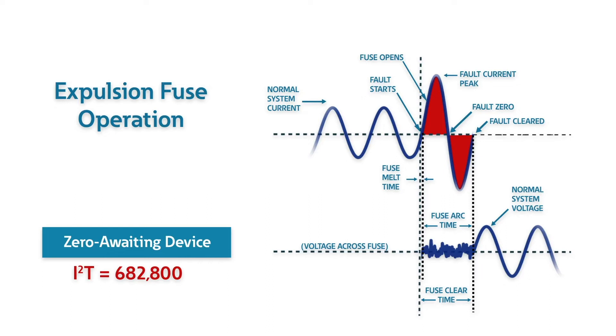The system voltage trace shows how the phase-to-ground system voltage drops during the fault clearing operation. This disturbance can cause some loads to have difficulty during operation and can negatively impact your underground cable in a riser pull application.